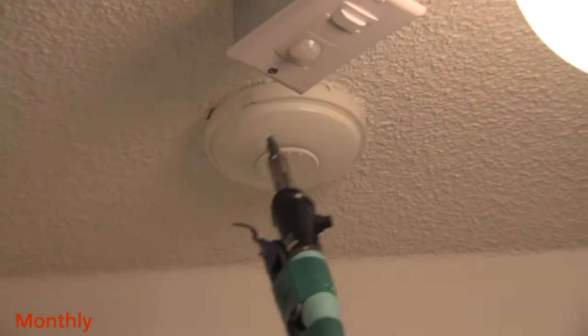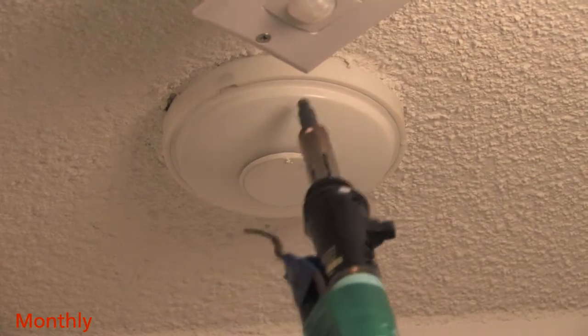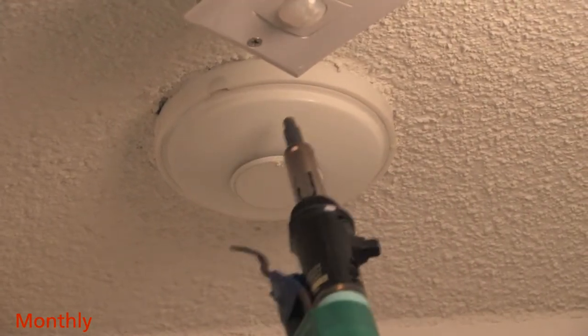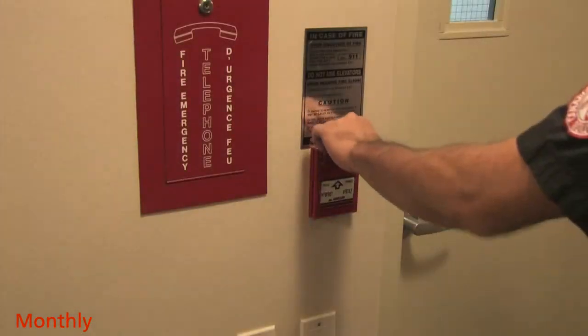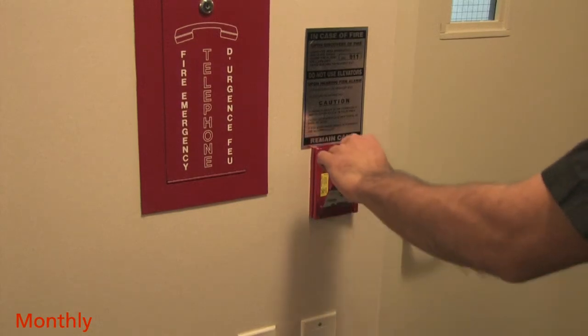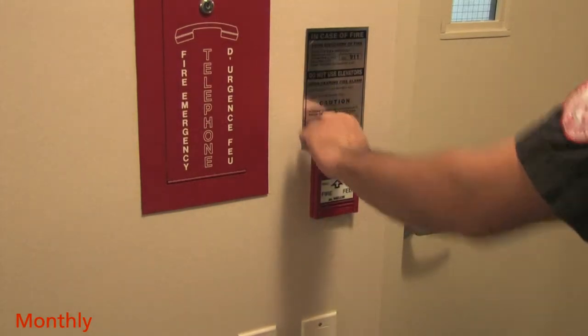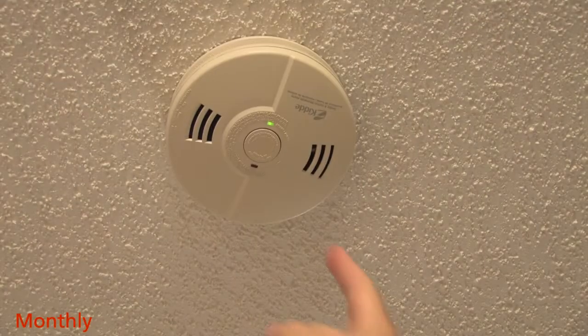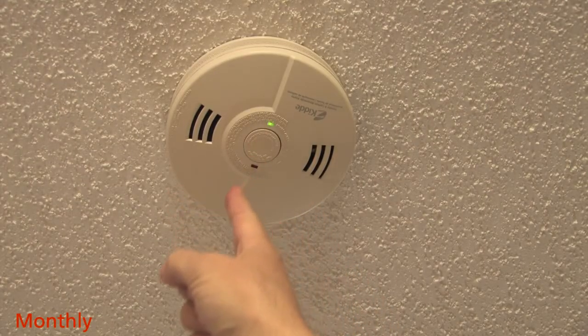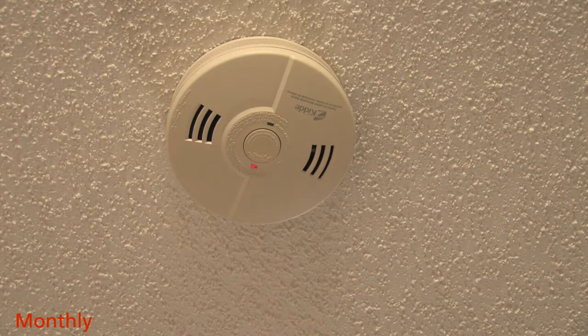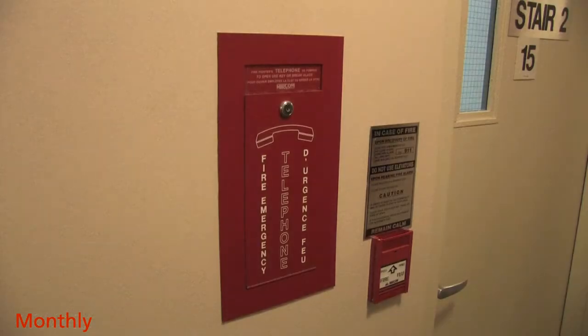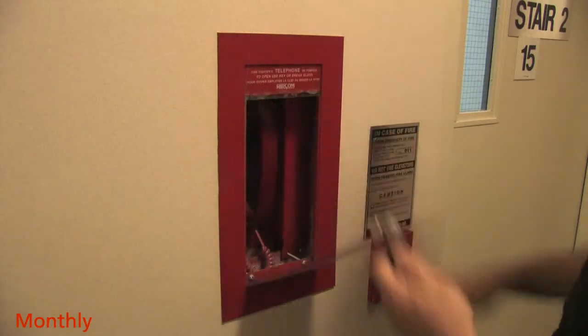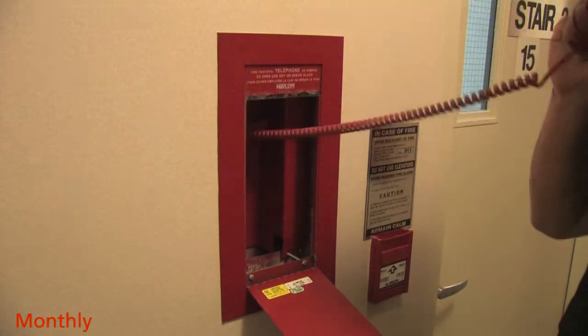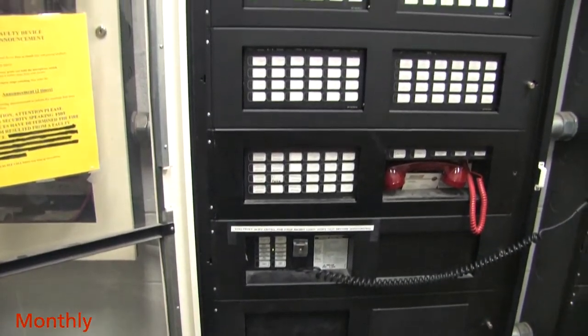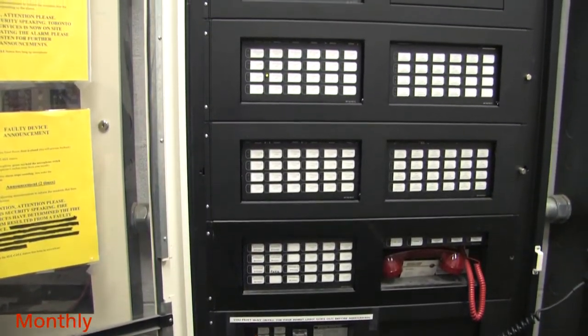Once a month, one initiating field device must be checked, such as a heat detector or water flow switch, or one manual initiating device such as a pull station. All devices should be checked on a rotational basis. Smoke detectors and carbon monoxide detectors, if installed, should be tested once per month on a rotational basis for proper operation. Depending on whether your building's fire alarm and voice communication systems are integrated, the following elements should be tested in each zone on a rotational basis.